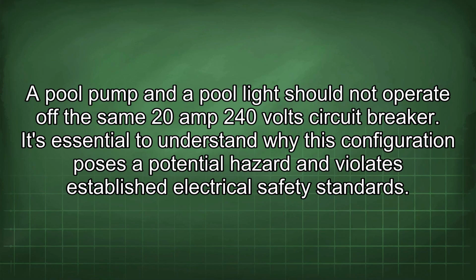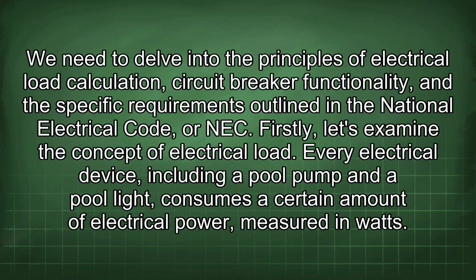A pool pump and a pool light should not operate off the same 20-amp 240-volt circuit breaker. It's essential to understand why this configuration poses a potential hazard and violates established electrical safety standards. We need to delve into the principles of electrical load calculation, circuit breaker functionality, and the specific requirements outlined in the National Electrical Code, or NEC.